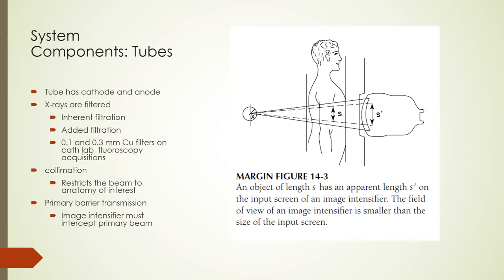On the x-ray tube side of image acquisition, fluoroscopy machines have a tube inset containing an anode and cathode. X-rays are produced when accelerated electrons from the cathode strike the anode. X-rays are filtered as they exit the tube port. Filtration removes the low energy components from the beam; added filtration improves beam quality. Filters are made of various thicknesses of copper and aluminum depending on the usage — for example, cath labs typically use between 0.1 and 0.3 millimeter copper filters on fluoroscopy acquisitions to reduce patient dose. Outside of the tube port, the x-ray beam is restricted to the anatomy of interest by collimating the beam using variable aperture collimators.